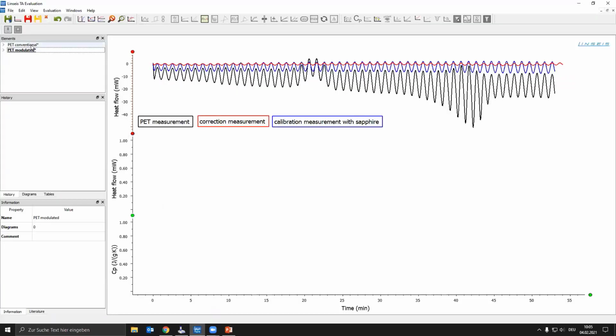Last but not least, it's possible to perform your sample measurement. And now, of course, you don't know what material it is, or if you know it, it doesn't affect the measurement itself. And you have to type in the sample mass and, of course, change the name. Everything else, again, is the same for temperature modulation and also temperature profile. Also here, you just have to start the scheduler and wait until the measurement has finished. Now, let's talk about the results.